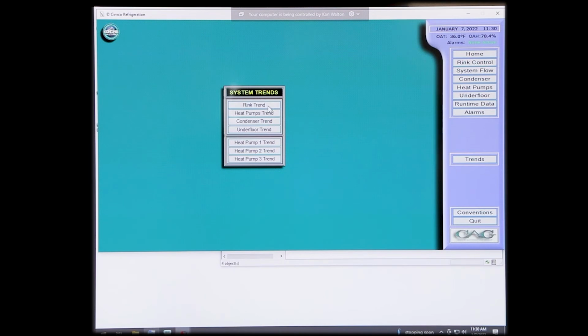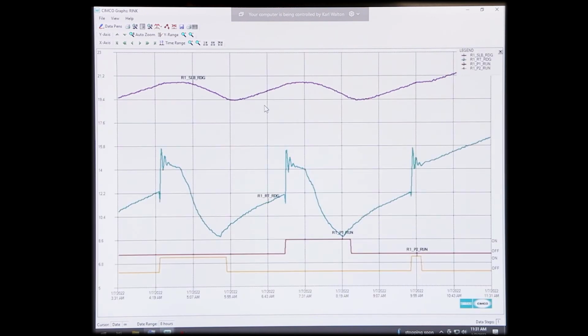So within system trends, you have a Rink trend, heat pumps trend, condenser trend, underfloor trend, and then individual heat pump 1, 2, and 3 trends. Okay? So we can look at different things. So here we go with Rink trend. And this is one of the things you guys are going to be able to look at daily to see exactly how did you do. Can I raise my temperature higher? Sure, you can try 0.5 degree. You can try 0.2 of a degree. If you save money, if you save energy, your ice is great, you may as well do it.